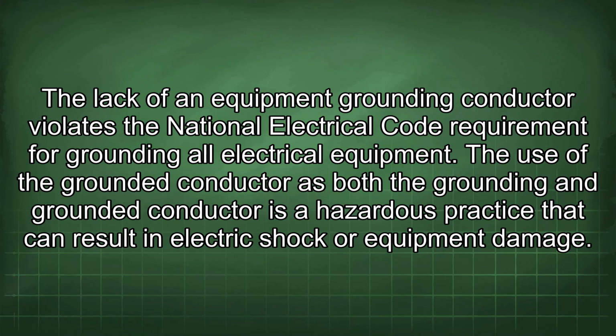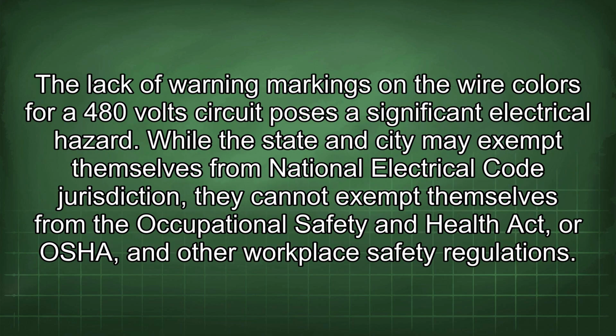The lack of an equipment grounding conductor violates the National Electrical Code requirement for grounding all electrical equipment. The use of the grounded conductor as both the grounding and grounded conductor is a hazardous practice that can result in electric shock or equipment damage. The lack of warning markings on the wire colors for a 480-volt circuit poses a significant electrical hazard.